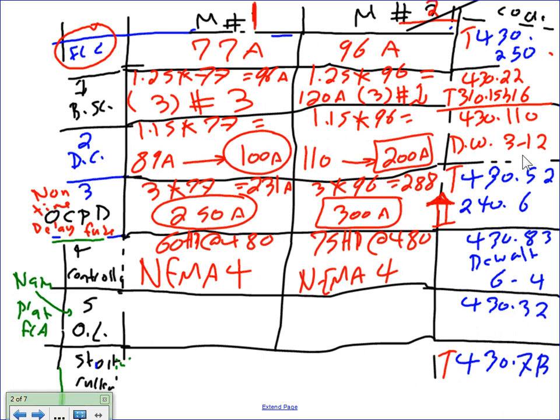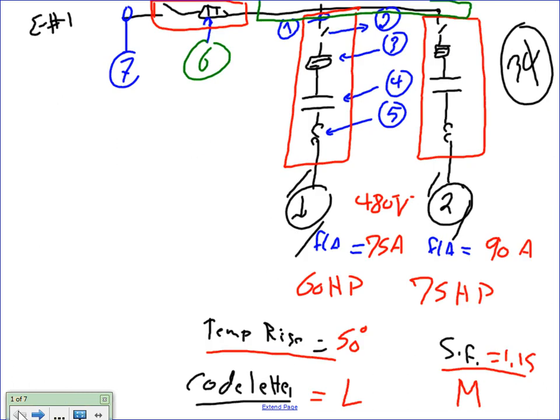Let's go to the overload. I want to remind you of two things for the overload. Overloads are kind of weirdos. We have a temperature rise of 50 here and a service factor of 1.15. The code says if the service factor is 1.15 or larger, the multiplier is 1.25. If the temperature rise is 40 or less, I do 1.25. Otherwise, I'm going to do 1.15. So please pay attention to the 50 and the 1.15 when it comes to the overload.